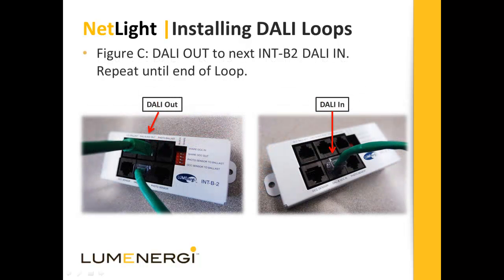Build out the DALI loop by connecting one interconnect box to the next using the provided DALI cables from the DALI Out port to the next DALI In port. Repeat this step until reaching the end of your loop. Keep in mind, each loop can only support up to 64 DALI devices. Lumenergi recommends attaching no more than 54 DALI devices per loop for future expansion purposes.